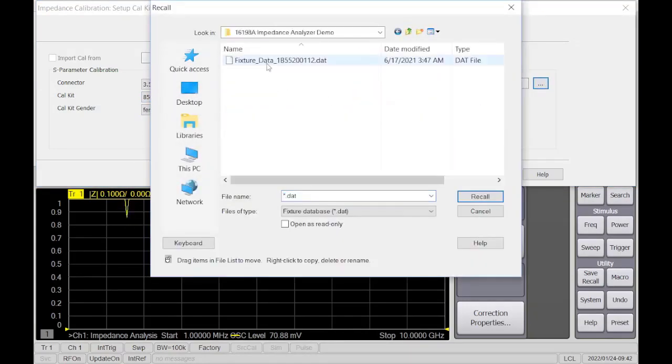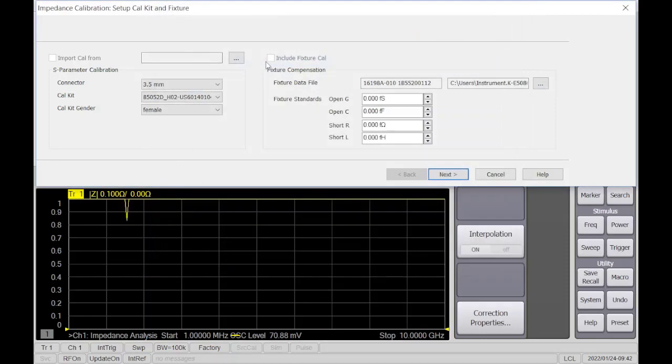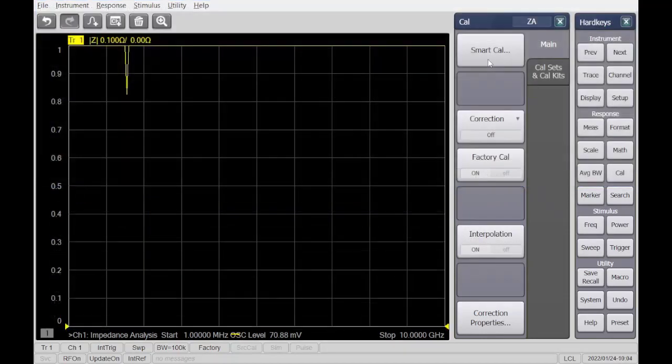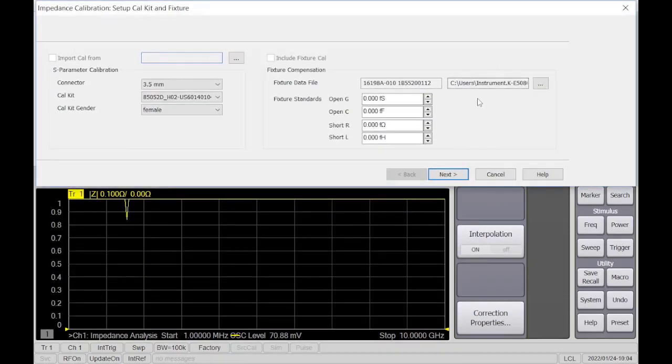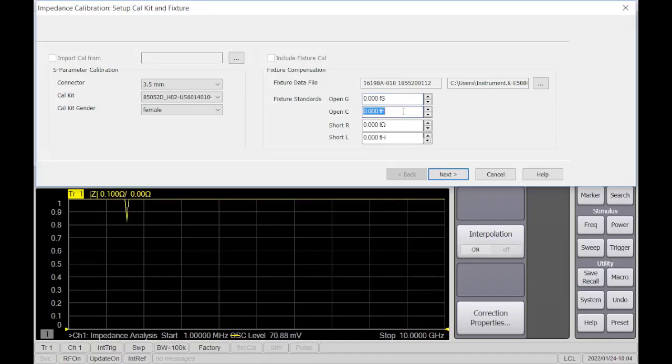Lastly, enter the open and short measurement values for the fixture. Recommended values are in the ENA help file. Open G, zero Siemens. Open C, 7.5 femtofarads. Short R, zero ohms. Short L, 0.19 nanohenries.